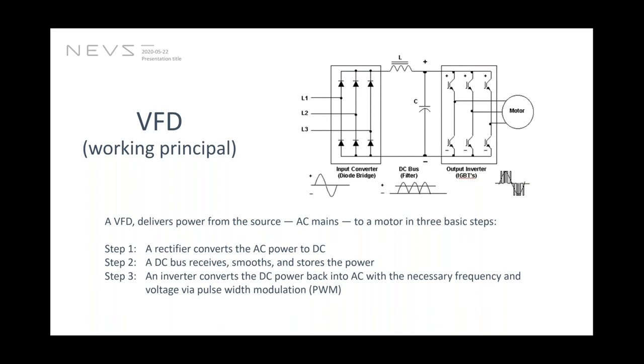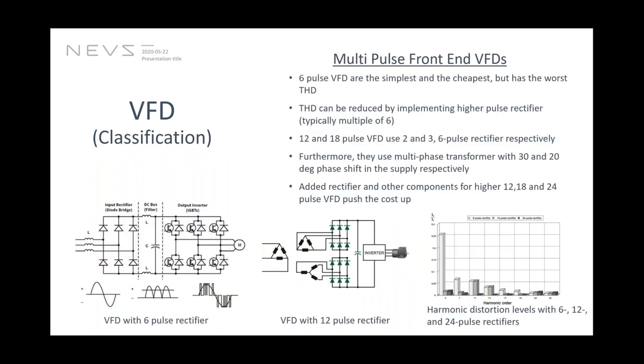So this is basically the working principle, and based on the products that are available in the market, I can categorize the VFD classification into two types. One is the multi-pulse front end VFDs, and the cheapest and simplest one is the 6-pulse VFD, as you can see in the figure in the left bottom corner. It uses a 6-rectifier bridge to convert the input AC into a DC for the DC bus. This is the cheapest and simplest, but worst in the harmonic distortion.